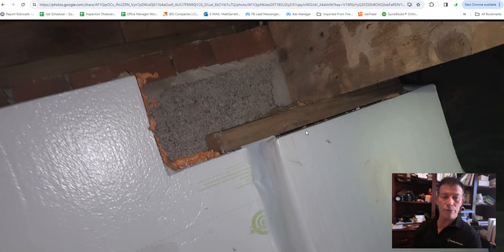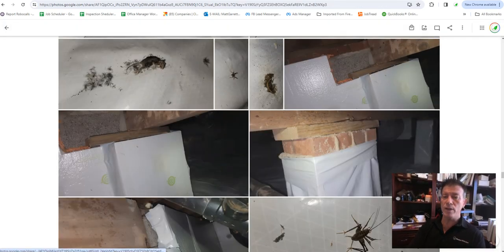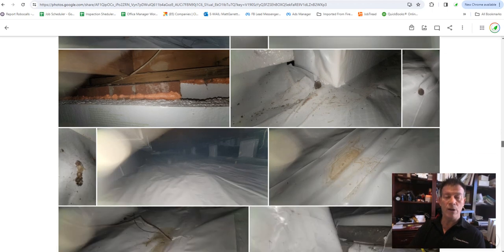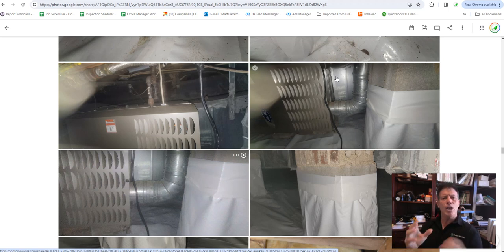Yeah, I'm gonna get styrofoam board. And yeah. So a big one too was the AC unit inside there. Once you seal off a crawl space and you have a gas furnace inside the crawl space, it needs to breathe fresh air. So there's usually a fresh air intake on a sealed crawl space per North Carolina building code, and then there's the exhaust that goes out at a 3 or 5% grade, all depending on the year it was installed.